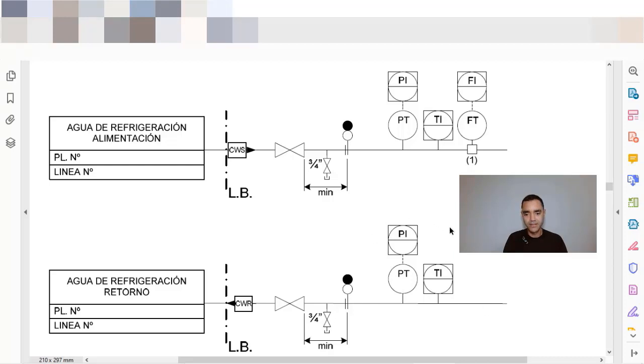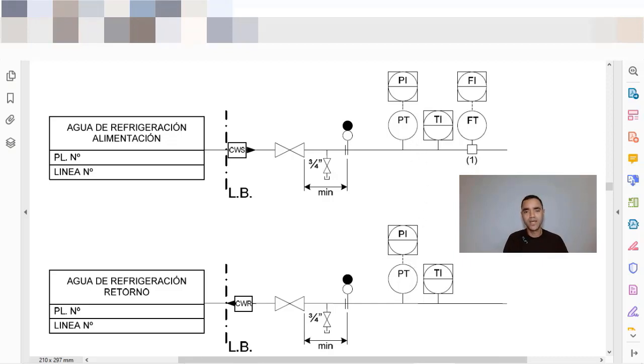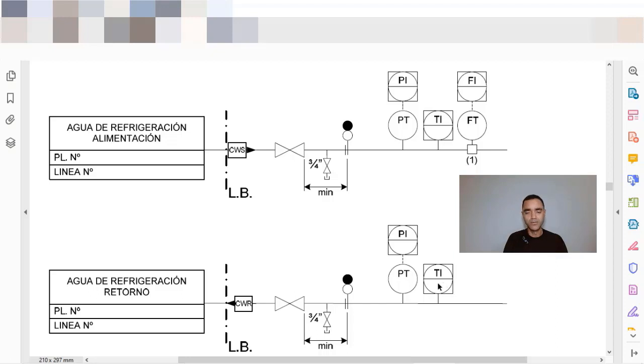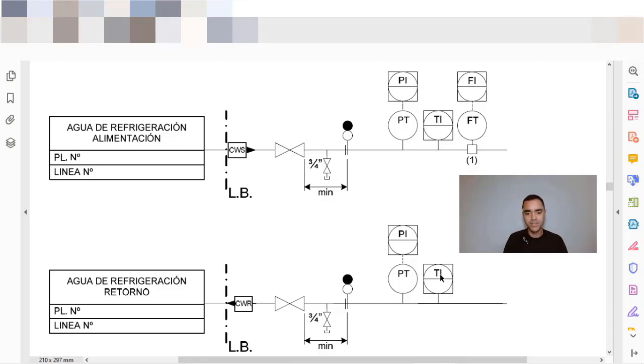And this is important just to a matter of verification of the efficiency of the system. If the differential pressure increases too much, it means that you have some obstruction in your heat exchangers, for instance. And if your temperature decreases too much, you can have also some kind of inefficiency in the equipments and they need to be cleaned. So that's why it's interesting to have the pressure and temperature in the return side for evaluation of the efficiency of the equipment.